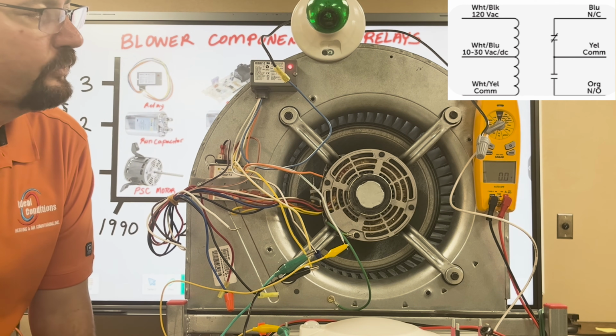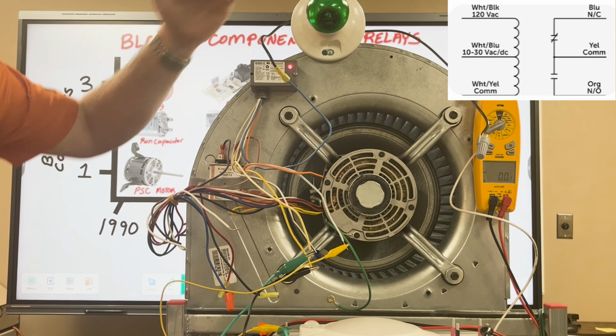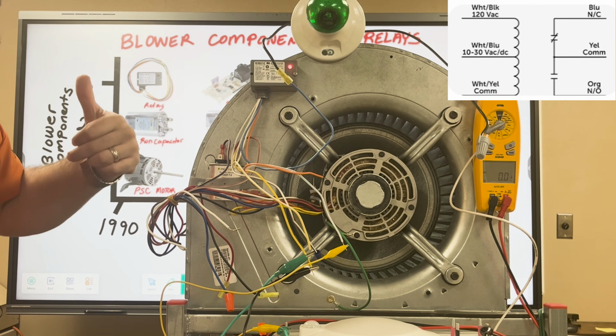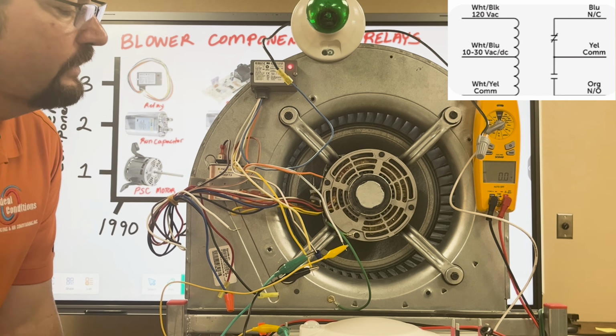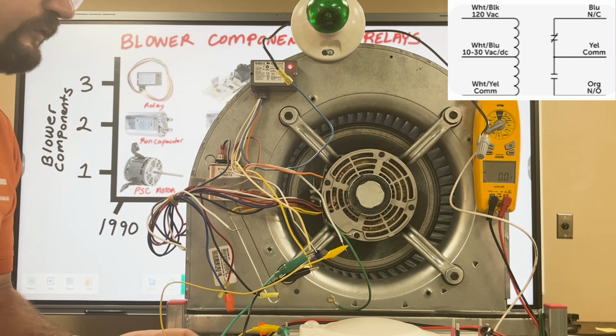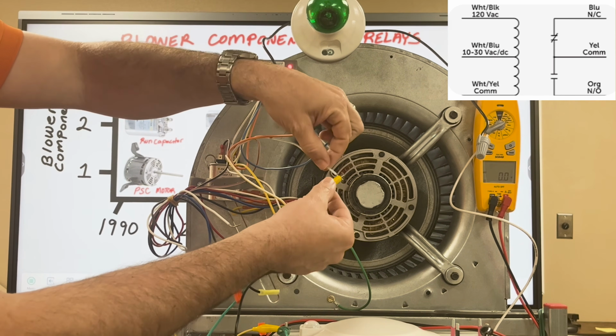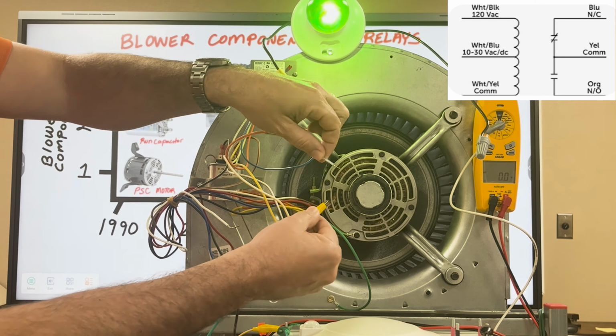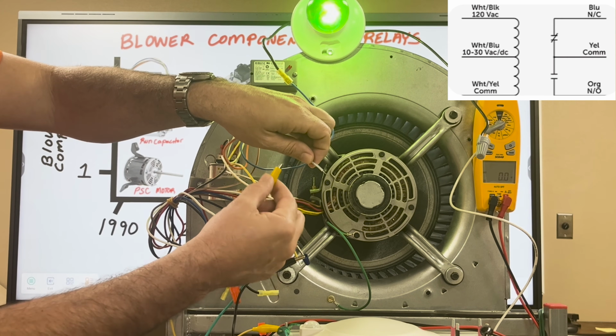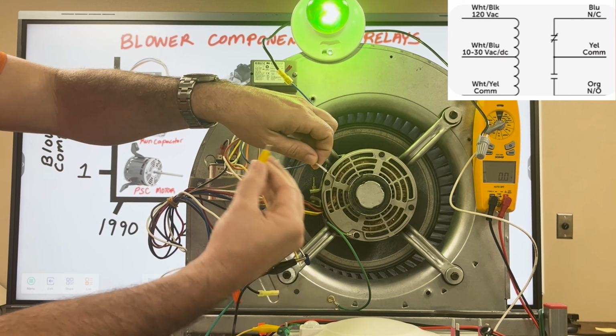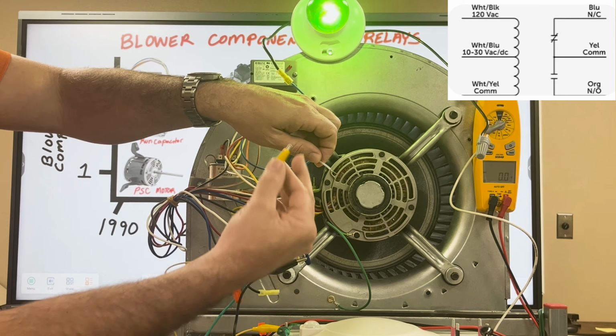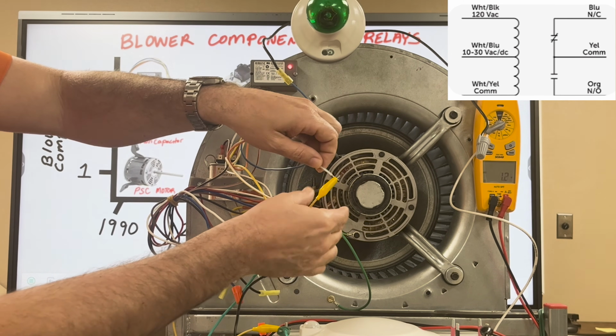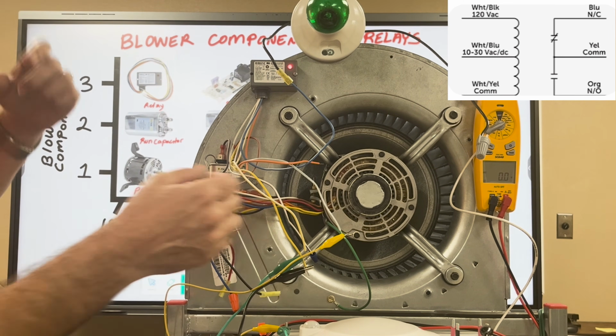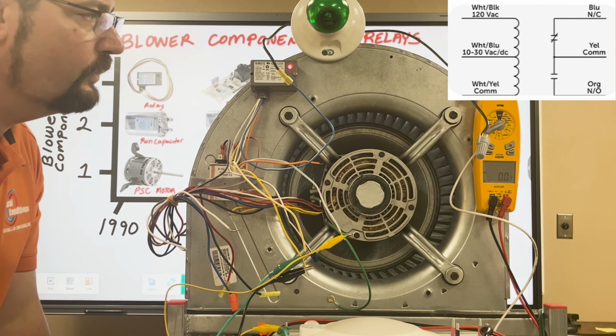And because I was wired to the normally closed side, obviously that opened the moment that we applied 24 volts there. So I'm going to go ahead and unwire that. You see we lose the 24 volts. The red light goes out. Normally closed is now engaged, and the green light is on. There we go. So we're pretty much going to do the same thing with the motor.